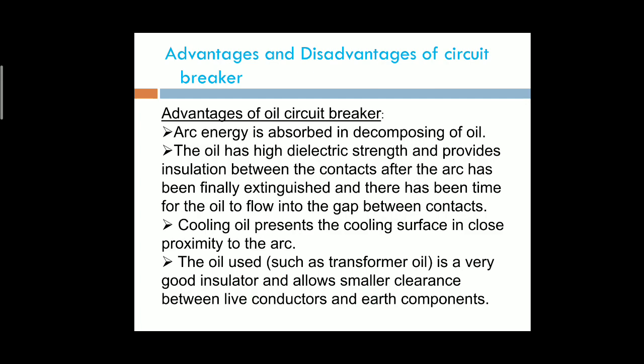The arc energy is absorbed in the decomposition of the oil. By decomposition of the oil, the arc energy is absorbed. That is one of the main advantages of oil circuit breakers. Next, the cooling oil presents the cooling surface in close proximity to the arc.